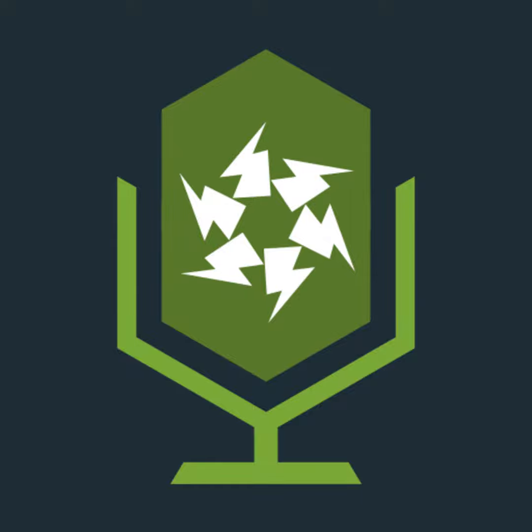You have different connection types illustrated here. I strongly suggest you observe the manufacturer's requirements with connection types anyway, but it does illustrate different connection types with regards to the configuration that is required. CT1 and CT2. Basically, a 4+0 configuration or a 3+1. Depending on the positioning of an RCD would also determine your connection type as well.